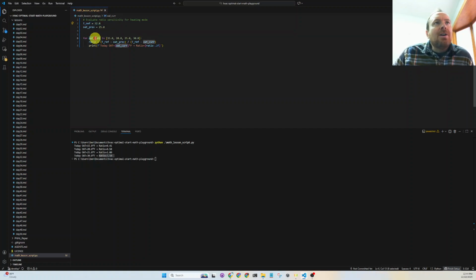So basically, we would have to be pretending that the building hasn't started yet from the building automation system, and our zone temperature has drifted from occupied set point because the equipment is off. So we'd be in a heating application. Basically, our zone temperatures would be cold, and we'd be needing to warm the building up before people arrive in an optimized fashion.